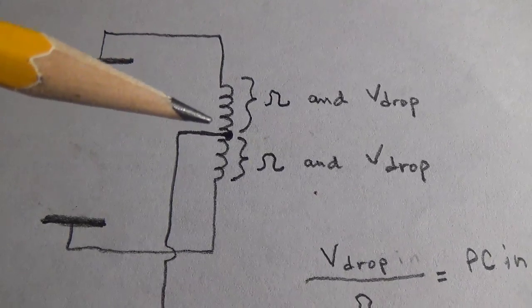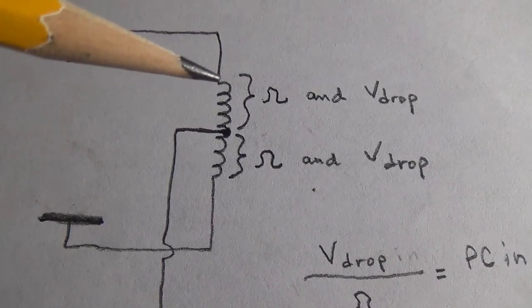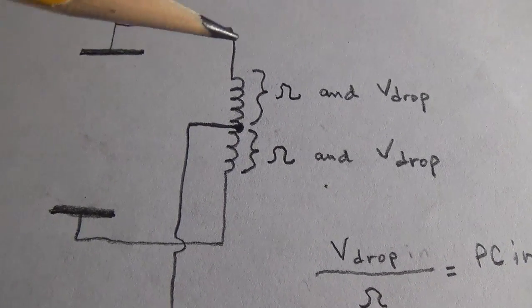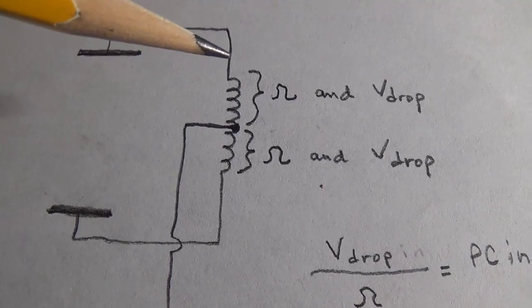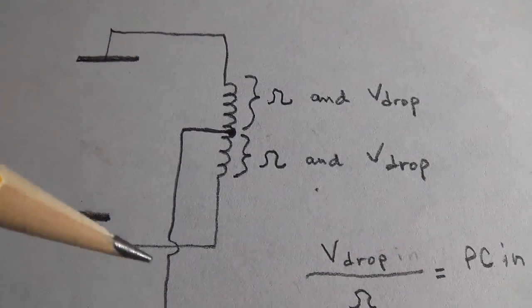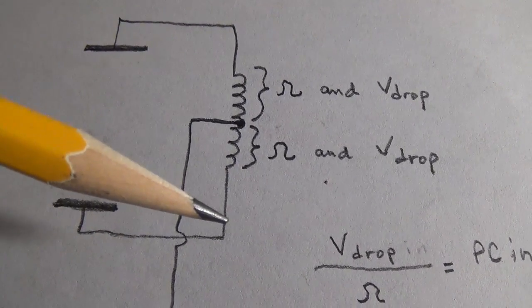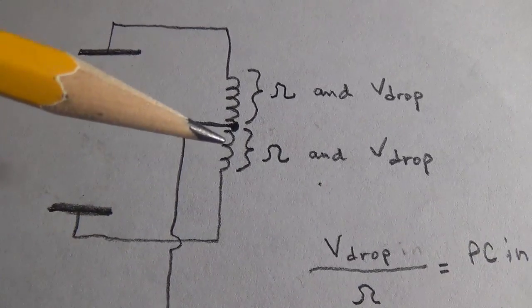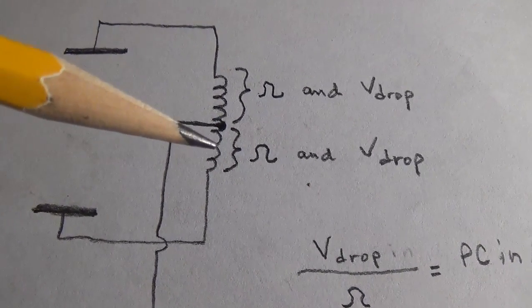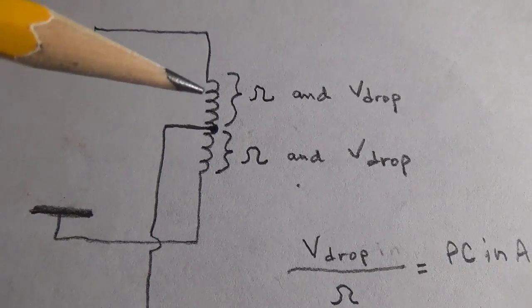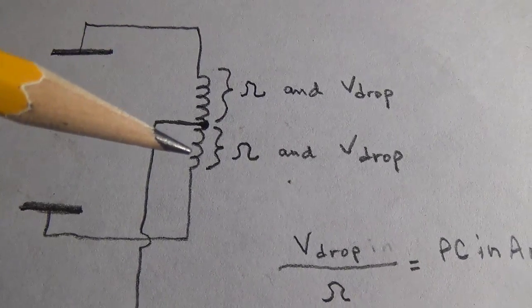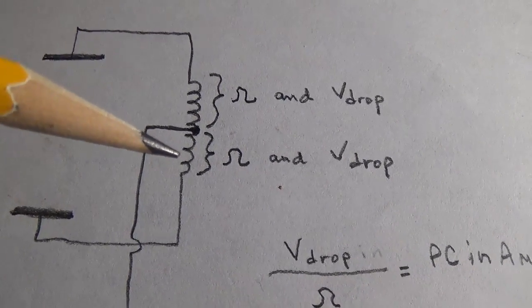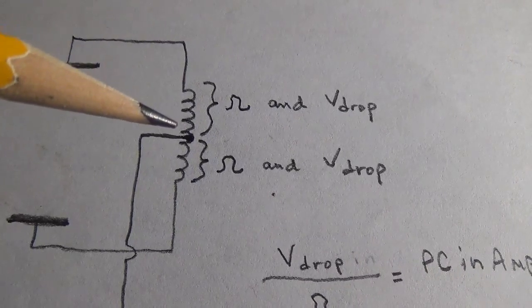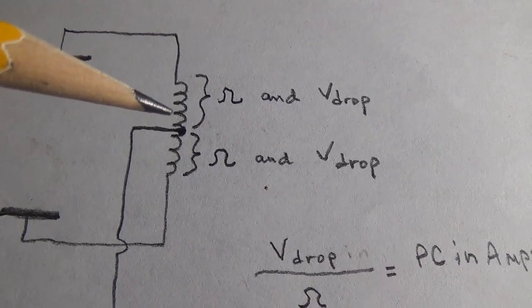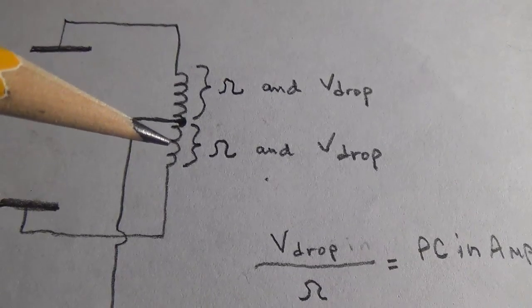Once we have measured the resistance across this half winding, we'll take one of our probes away from the upper plate and clip it onto the lower plate and measure the resistance of that half winding. Since I say half winding, you'd think these 2 values would be the same, but they never are - no output transformer is wound exactly the same. So you've got to do both measurements.